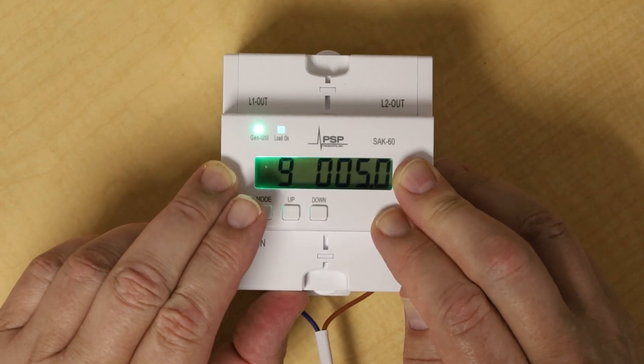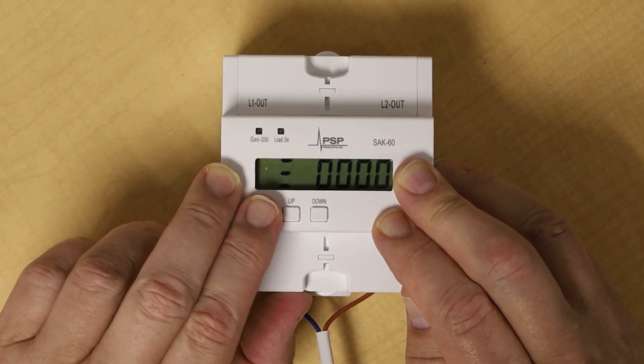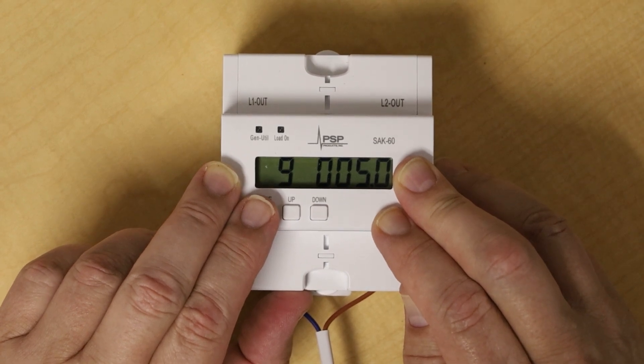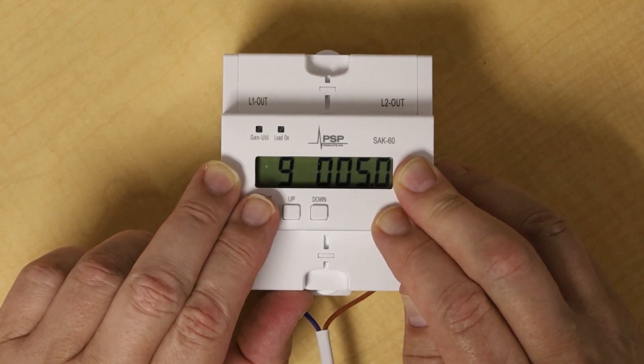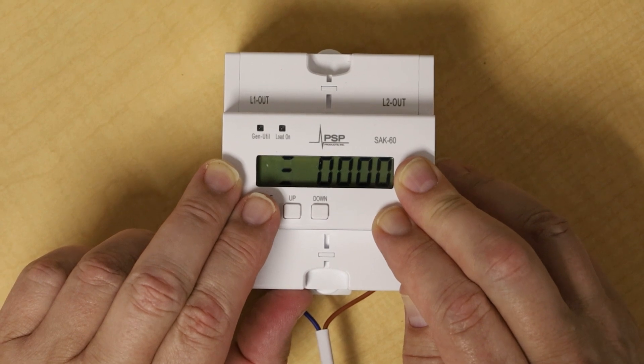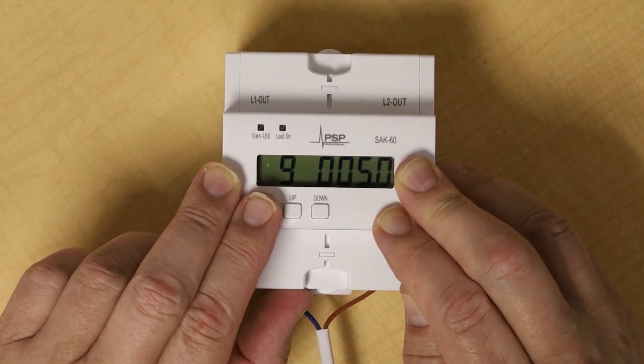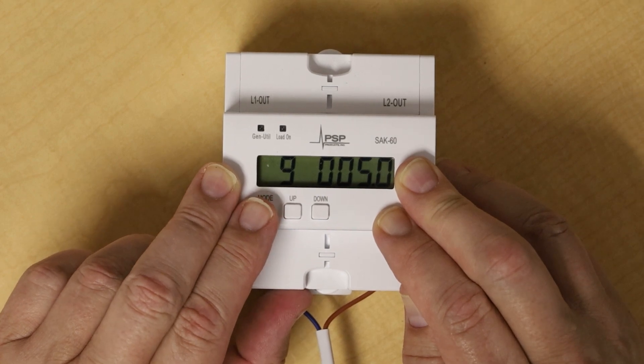This will be set to 5 minutes by default. You can leave it there for the first SAK60 on a system, but for additional SAK60s on the same system, you should stagger that by 0.5 or 30 seconds to stagger the on time of your various loads.